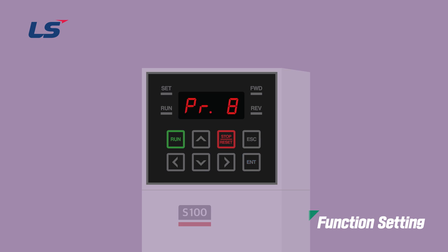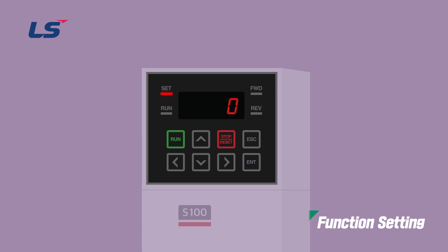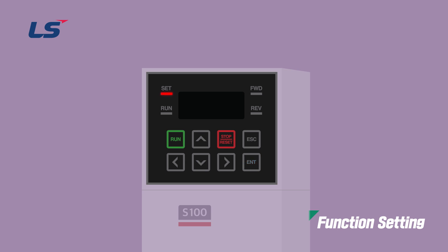Set the number of Auto Restarts in PR09 and the Auto Restart delay in PR10. For this video, we'll set the number of Auto Restarts to 2 and the Auto Restart delay to 5 seconds. To create a trip situation for testing, set one of the multi-function inputs to External Trip. In this video, we will set the P4 terminal to External Trip. The P4 terminal function setting can be set in IN68.